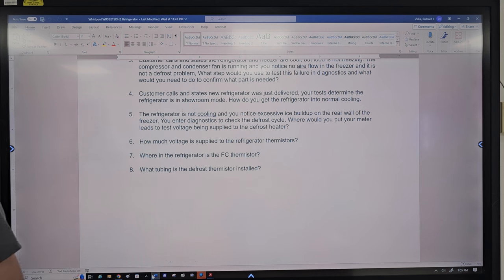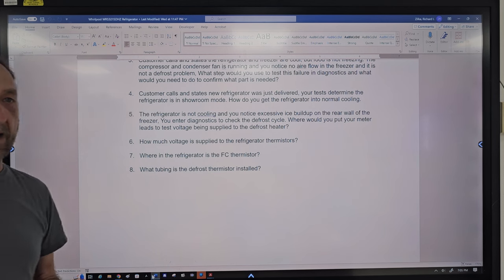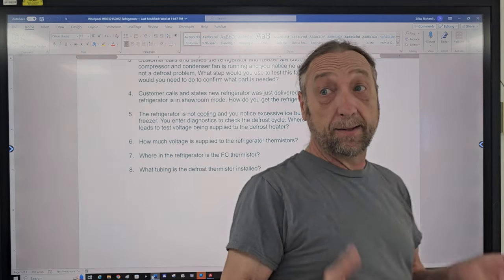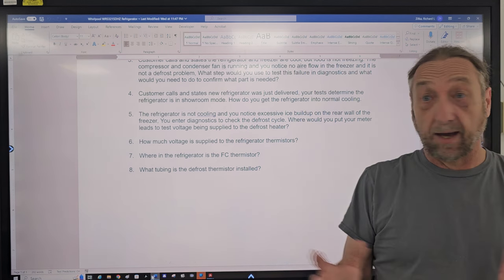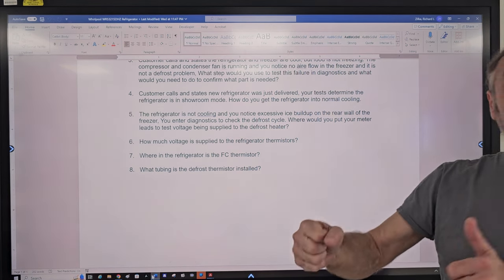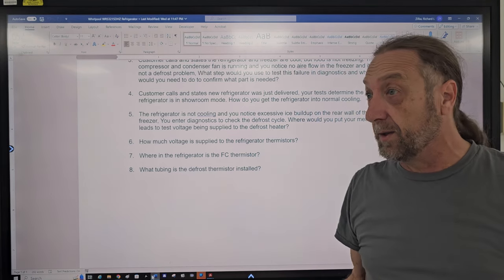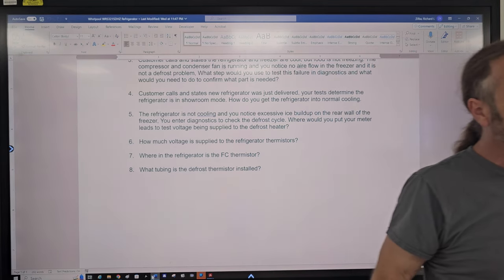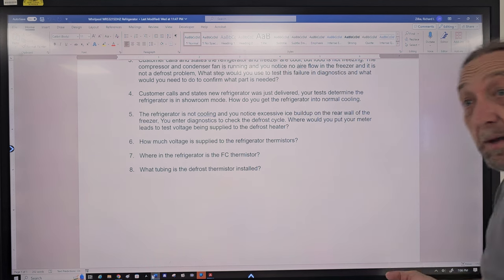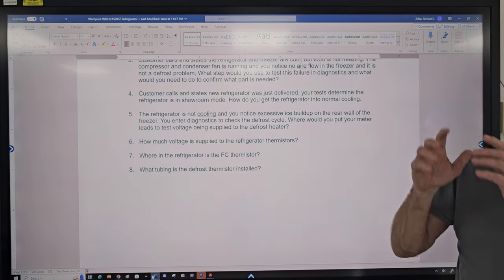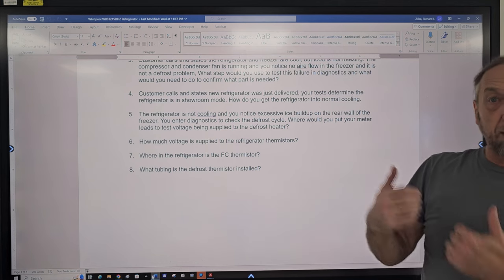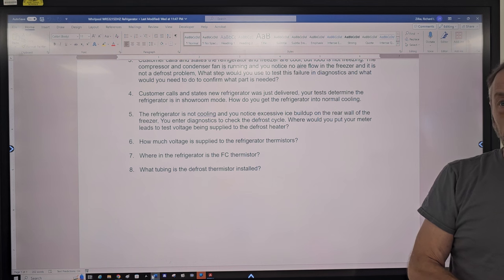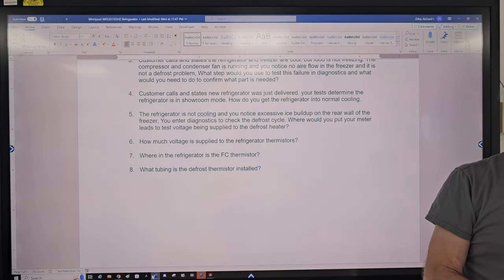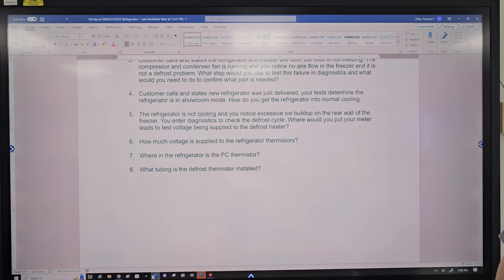The idea behind this assignment is I know how to get into diagnostics, but how do I use diagnostics, and when do I use a specific step? And once I'm using that step, what do I do with it? So, it's got a defrost problem. We know a heater melts the ice, so we've got to go into the step that's telling the heater to come on. But then we've got to see if the board's sending power, and if it is, we've got to check the components to find out which one failed. Any questions on that?